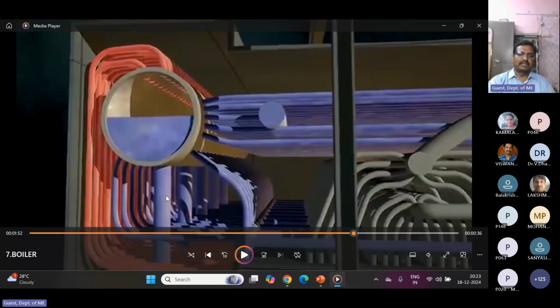After going downwards, there is a part called the bottom ring header. That is at the bottommost point of the boiler furnace. So it goes directly to the bottom ring header. From the bottom ring header, there are riser tubes, or water walls. The total furnace is covered with a number of tubes which are called water walls.